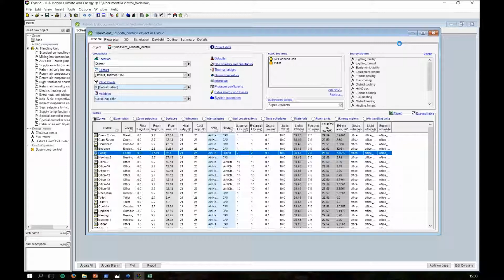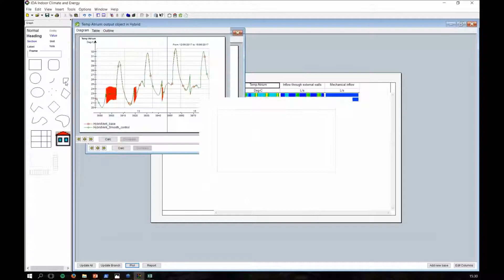To compare these, did I save? I think so. Yeah. To compare these, I'm going to look at the temperature in the atrium for both cases, plotted. And look at here. It's very, very interesting. Let's look at it by day. What is happening here is that the thermostat is trying to open this window and is cycling. This is a classic hunting effect in control. It's trying to open, but as soon as the window opens, the temperature drops and then it's trying to close it again. Whereas the proportional controller has a very, very smooth action here.